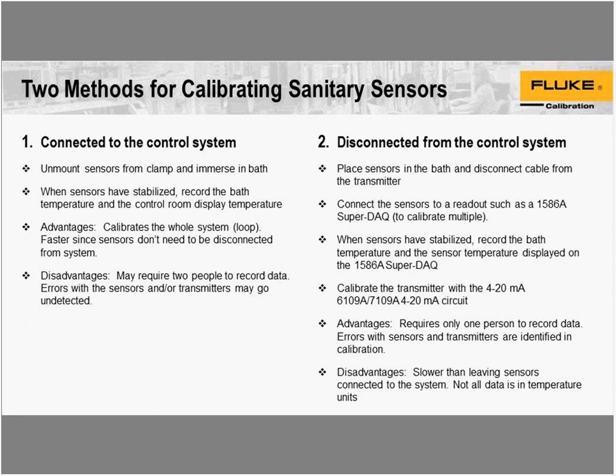And there's a possibility, too, that one disadvantage is that at a transmitter calibration, you may not be working in units of temperature, which can often be a challenge if you're working under FDA regulations. For example, FDA auditors seem not to appreciate seeing calibration data for a temperature system that's in some other units like amps or volts or ohms.